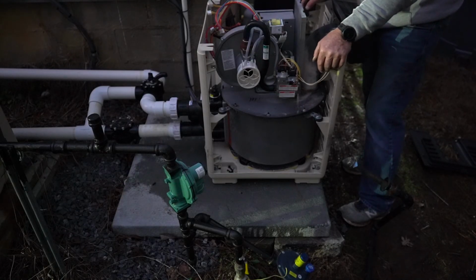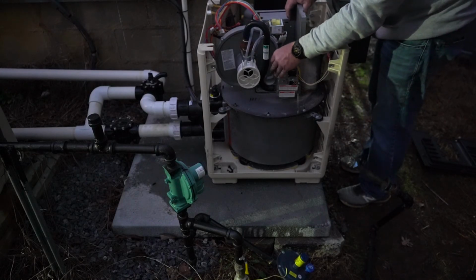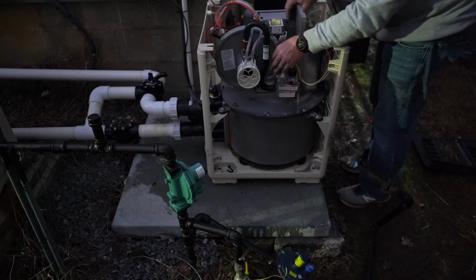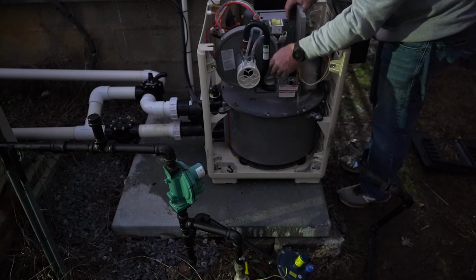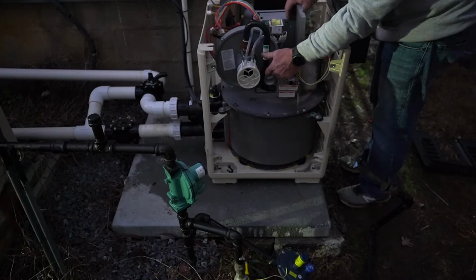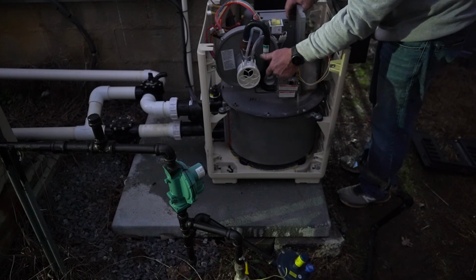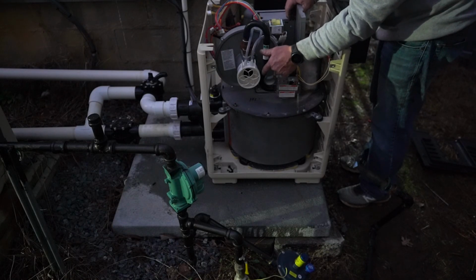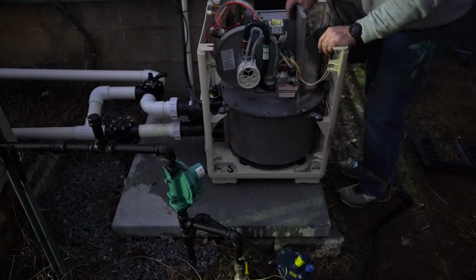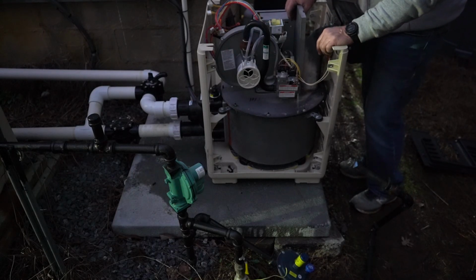We're going to have another video on how to test the gas pressure going into the gas valve, and also test the pressure coming out of the gas valve, right here. That's what we're going to worry about, because in this case this heater sooted up, so this gas pressure, which is a negative pressure, is either too high or too low, causing the flame to be either too rich or too lean.